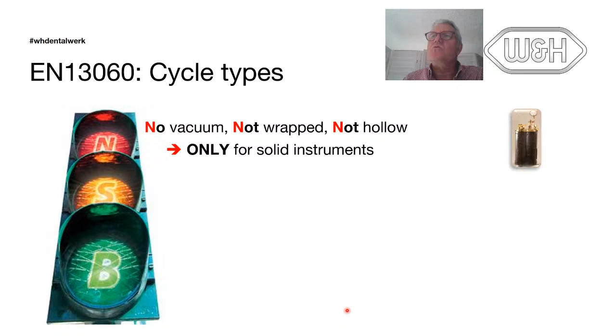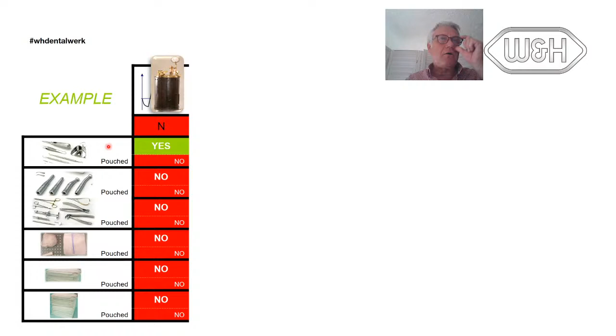You see here, this table shows the different type of instruments. There are actually 6 families, from solid, hollow, and porous. This machine can only do solid, non-pouched. And then you have different examples. Here is our MS machine. It can do solid, of course, up to 2 kilos. All this information must be provided by the manufacturer. 2 kilos is quite nice. You would never process more than 2 or 3 kilos anyway. It can process hollow instruments up to 1 kilo and porous instruments, porous loads, up to half a kilo. So it is a specific machine, specific cycle, but it's much better than the previous ones and much better than dry heat. And here you see the B-type cycle.